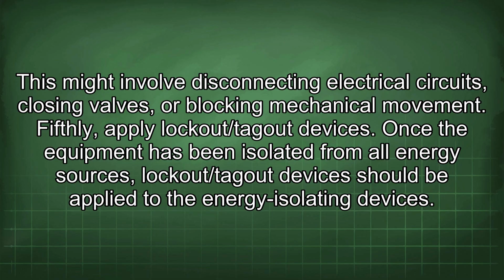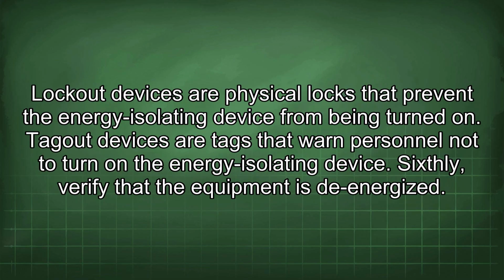Fifthly, apply lockout/tagout devices. Once the equipment has been isolated from all energy sources, lockout/tagout devices should be applied to the energy isolating devices. Lockout devices are physical locks that prevent the energy isolating device from being turned on. Tagout devices are tags that warn personnel not to turn on the energy isolating device.